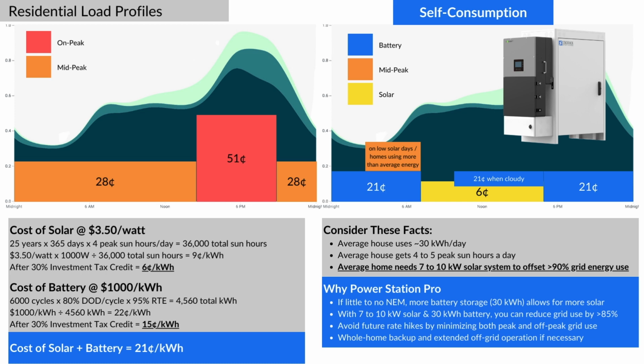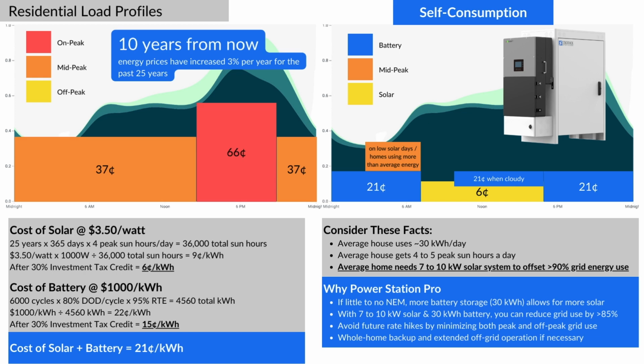And what I have shown here in the top right corner is our Power Station Pro, which has been designed exactly for that purpose. Using this hybrid inverter, this all-in-one setup, along with 30 kilowatt hours of battery storage, this single unit can convert the home into a microgrid, in which case you're only using the grid for power when your battery and your storage is not sufficient.